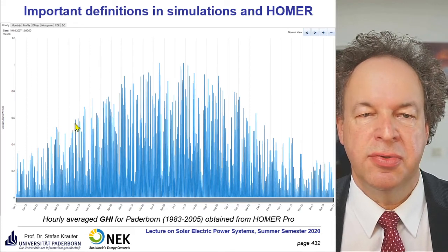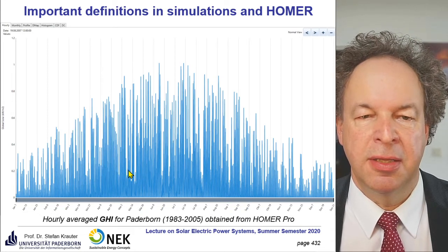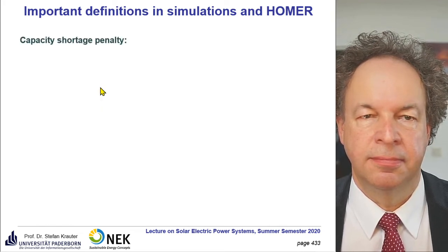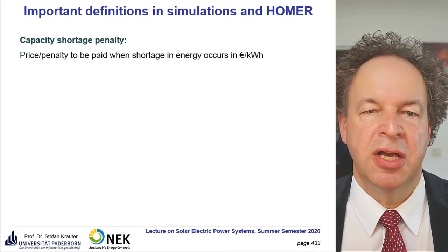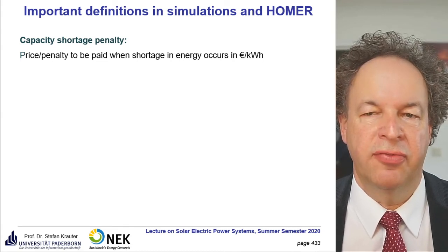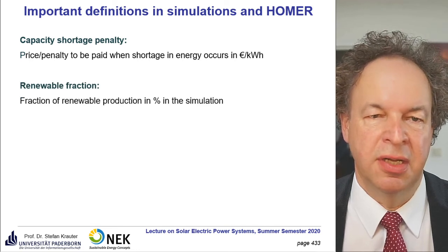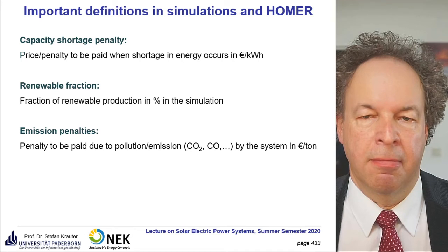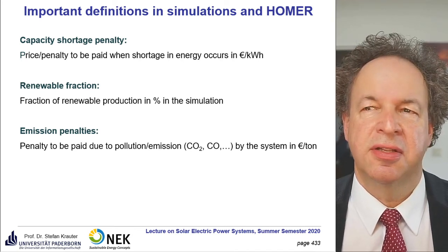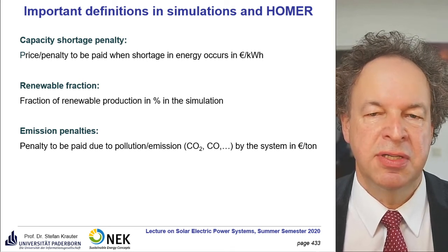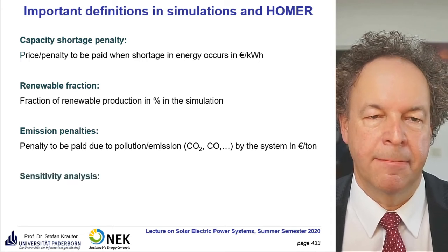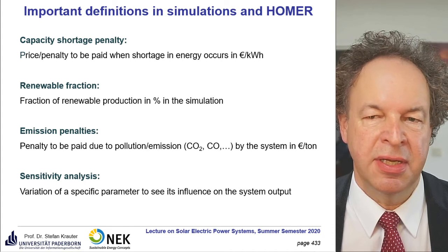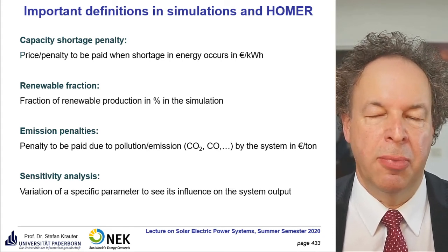The GHI for Paderborn shows a general seasonal change but also high daily variation depending on weather conditions. The capacity shortage penalty means you pay a fee for each kWh you don't deliver. The renewable fraction is the fraction of renewable production in the simulation. Emission penalties will be introduced — starting at 25-30 euros per ton of CO2 increasing to 55 euros in coming years. Sensitivity analysis is also very interesting: you can vary a specific parameter — inclination of a PV module or battery size — and see the technical and financial influence on the system output.